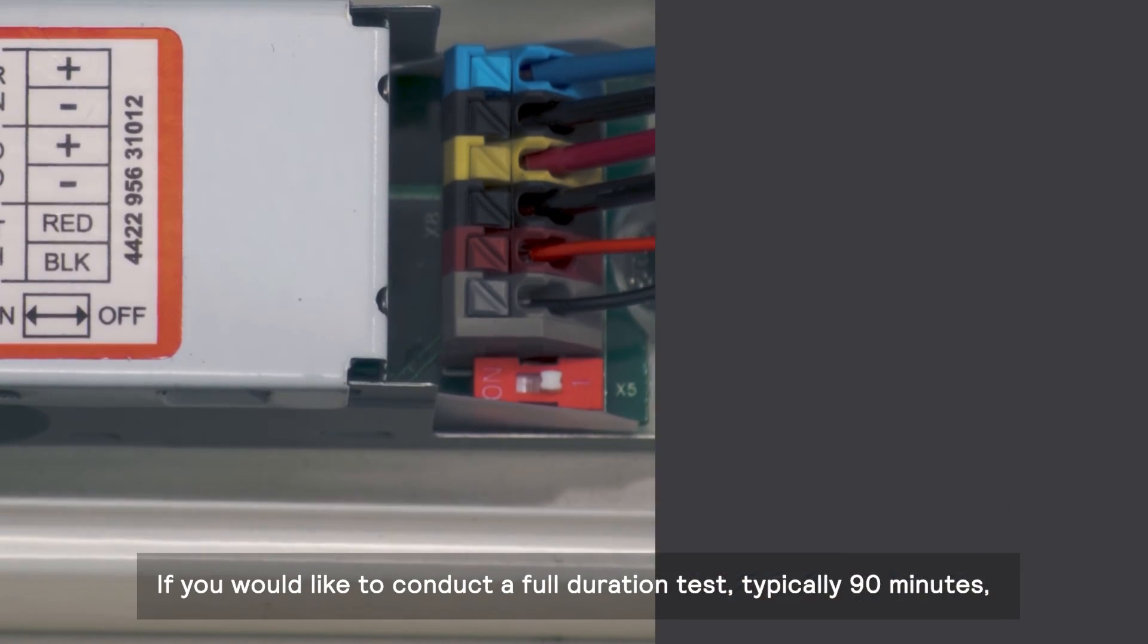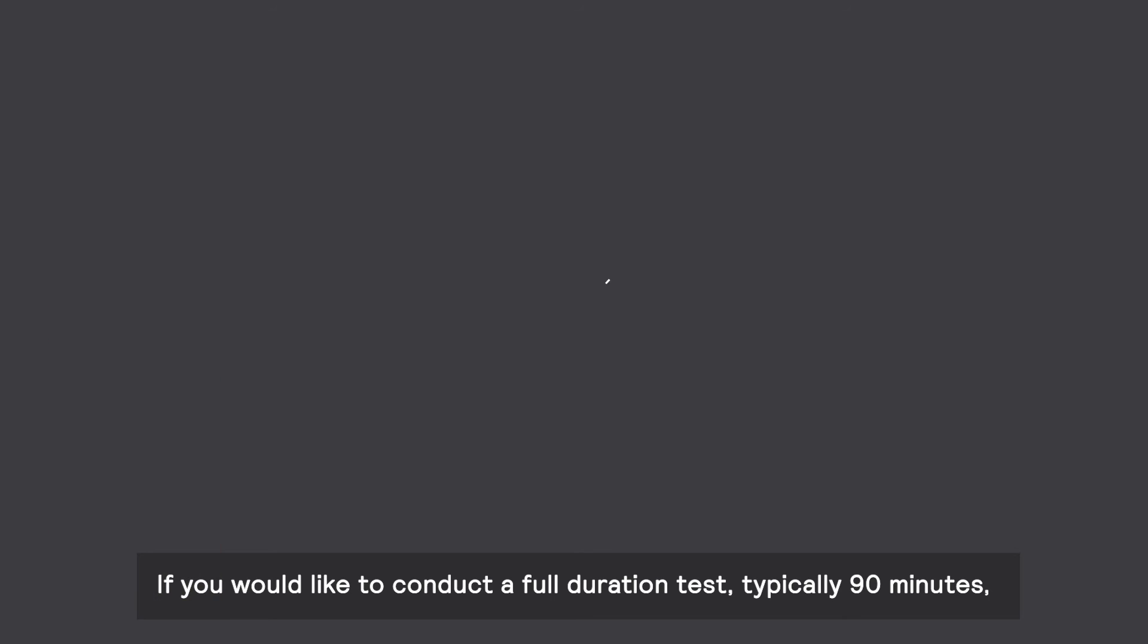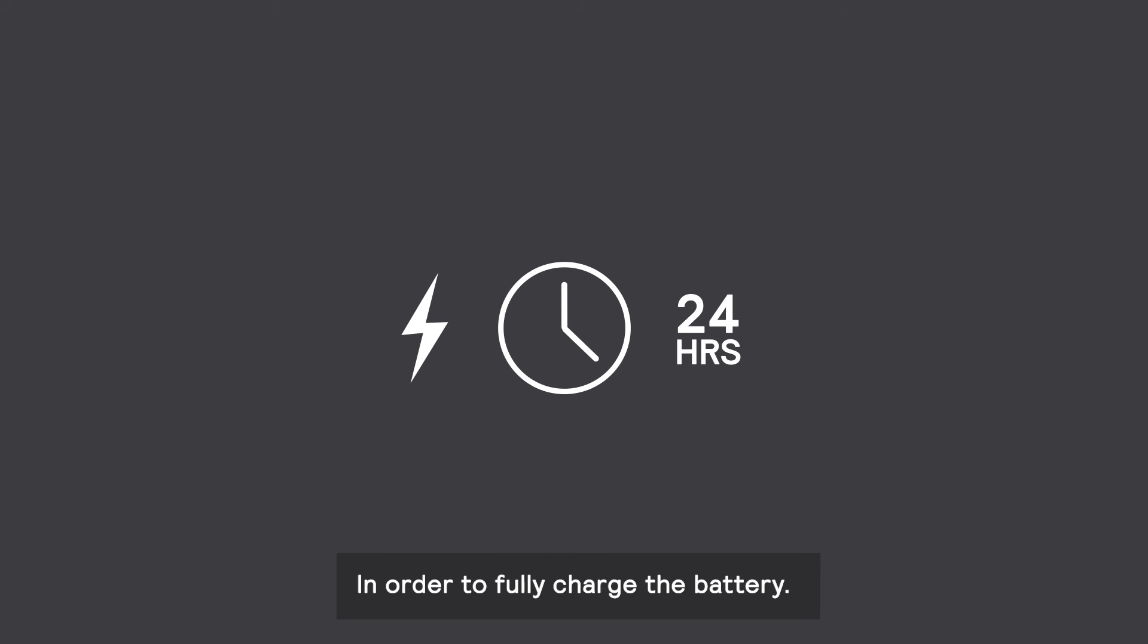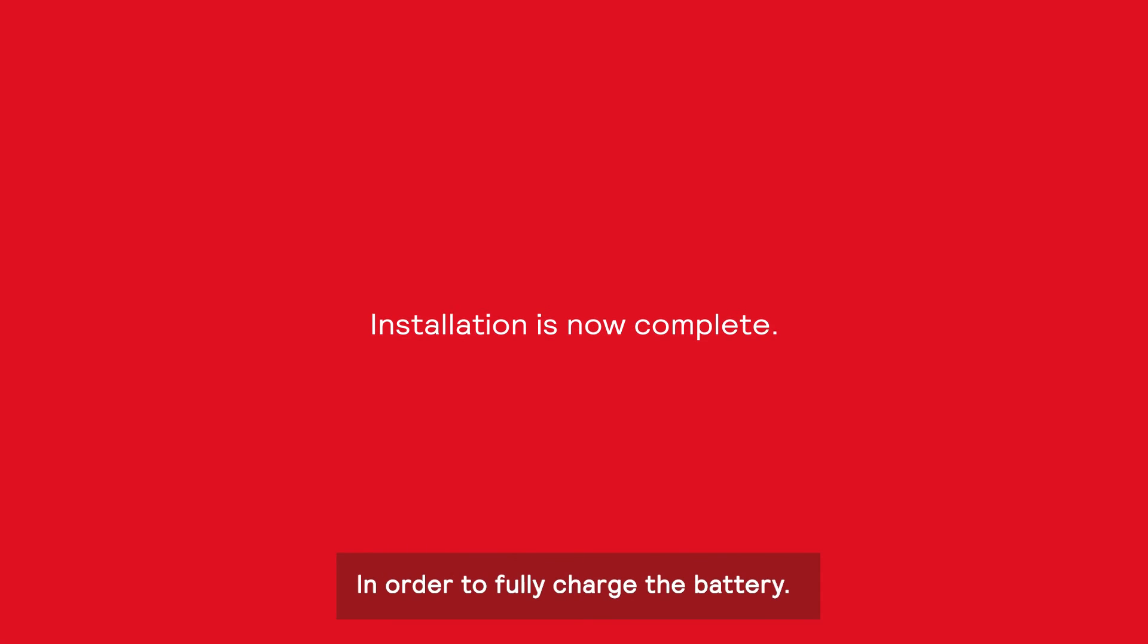If you would like to conduct a full duration test, typically 90 minutes, please allow the emergency driver to remain charging for at least 24 hours prior to testing in order to fully charge the battery.